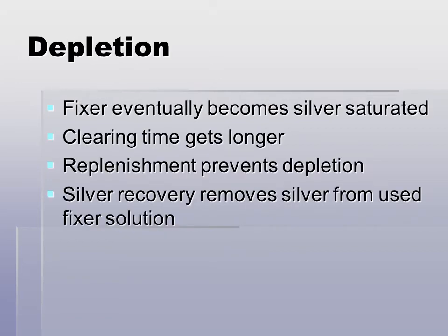Depletion. Fixer eventually becomes silver saturated. The clearing time gets longer, and replenishment prevents depletion. Silver recovery removes silver from used fixer solution. And we'll talk about that a little bit more with silver recovery and the replenishment systems.